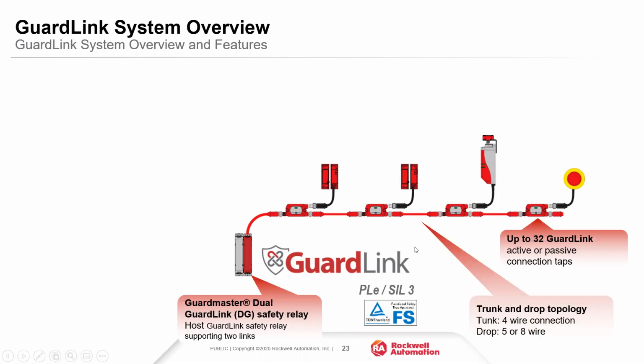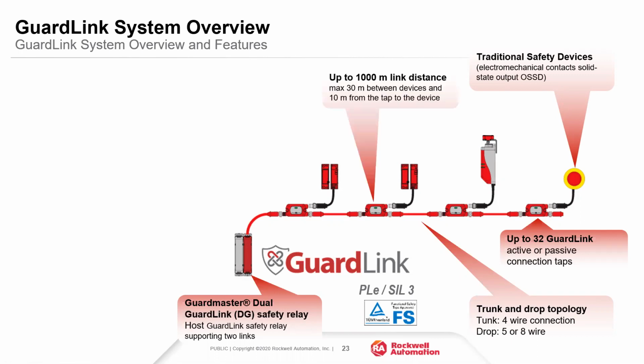And again, it's a standard trunk and drop. The wiring for the trunk is a 4-wire connection, and then from the device to the tap it's just a 5 or 8 wire, depending on what the device is. The devices can typically be any electromechanical device like an e-stop or an interlock switch, or a solid state device such as a light curtain, a laser scanner, and things like that. You can go up to 1,000 meters, 30 meters between taps, and then 10 meters from the tap to the device.